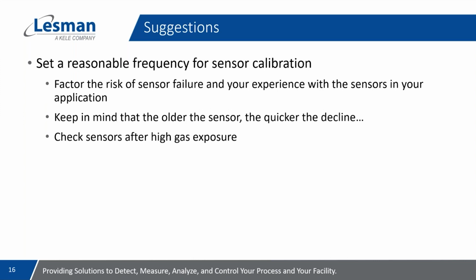So the takeaways: set a reasonable frequency for sensor calibration. To define reasonable, factor in the risk. If your team, for whatever reason, didn't respond to the gas alarm the way you wanted them to, how big of a deal would it be? What would the consequences be? Let that inform your frequency of self-check. Keep in mind that older sensors tend to drift more than younger ones, just like us. It takes me a heck of a lot longer to recover from a run than it did a few years ago. And by sensors, I'm not talking about the transmitter or the electronics. I'm talking about the sensing elements themselves. Typically, they drift more the older they get, the closer to end of life they get.